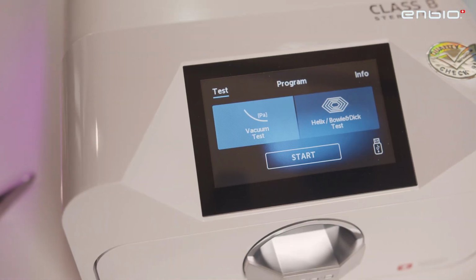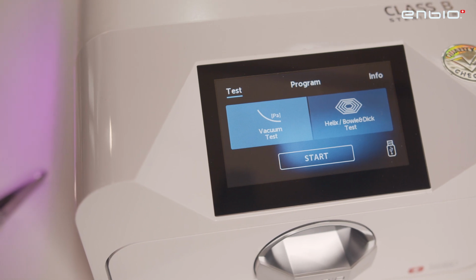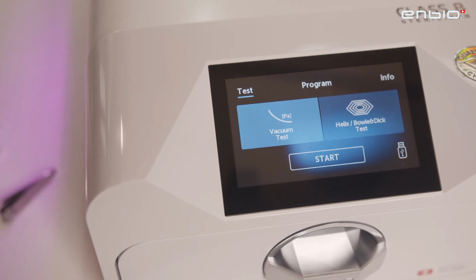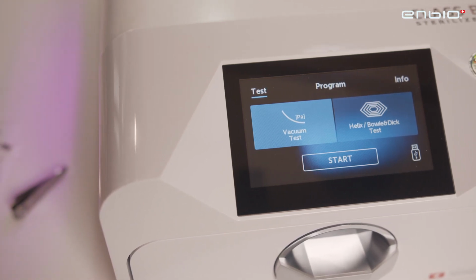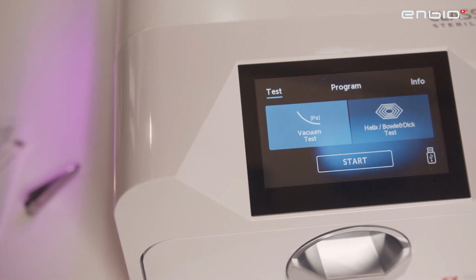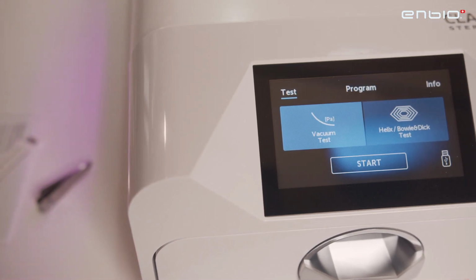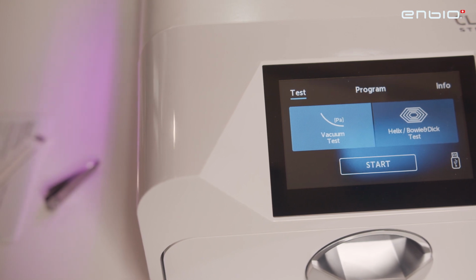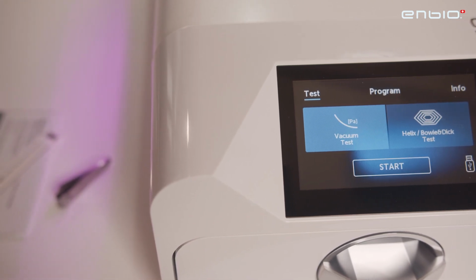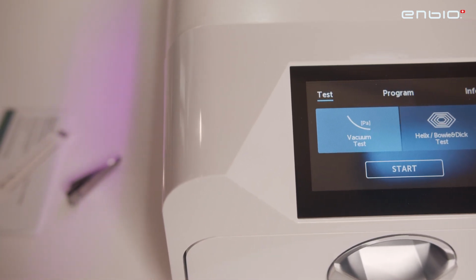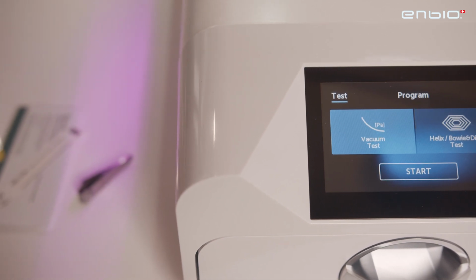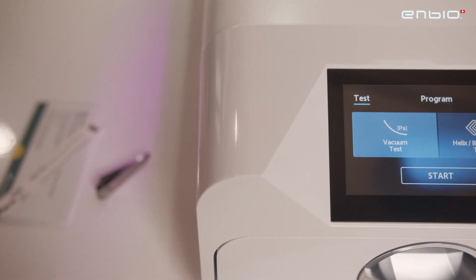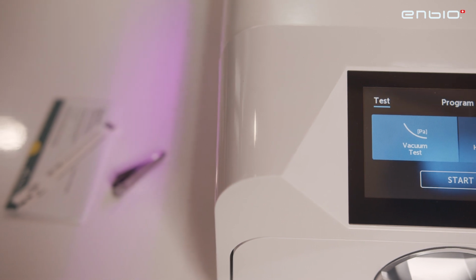One very important thing to remember is that we need to perform the vacuum test at the beginning of the working day, which is before we sterilize any other tools, because for this test, the autoclave has to be cold. So we recommend that if you use this kind of autoclave, like the Enbio autoclave, you perform the vacuum test every day before you start sterilizing any other tool.